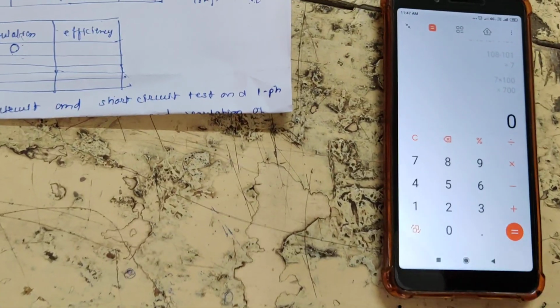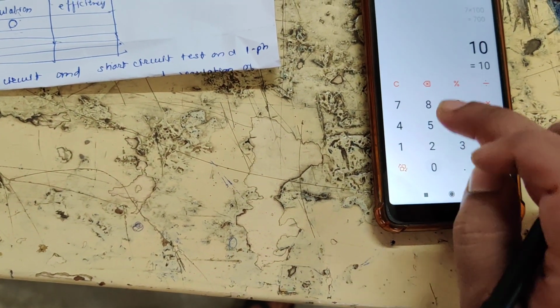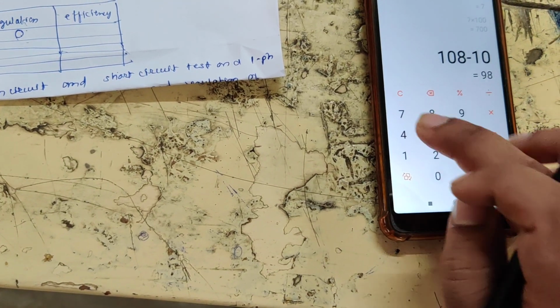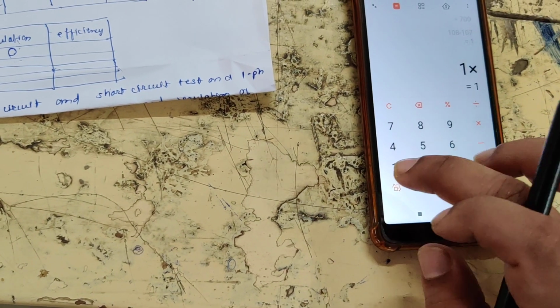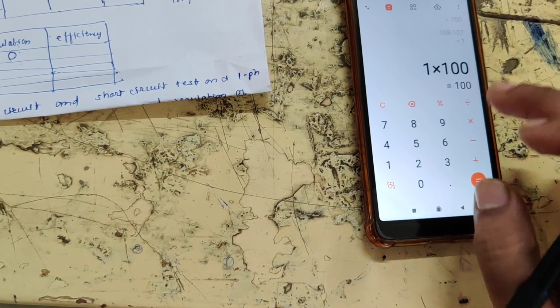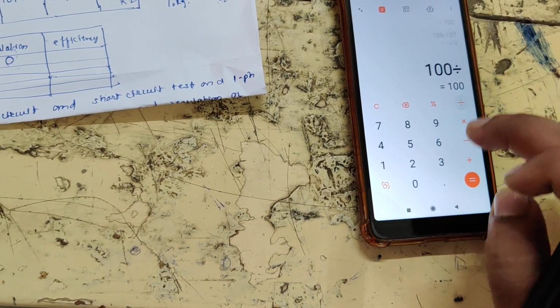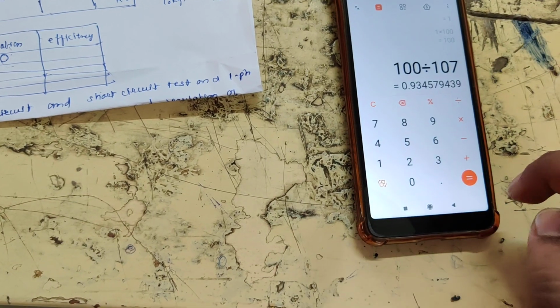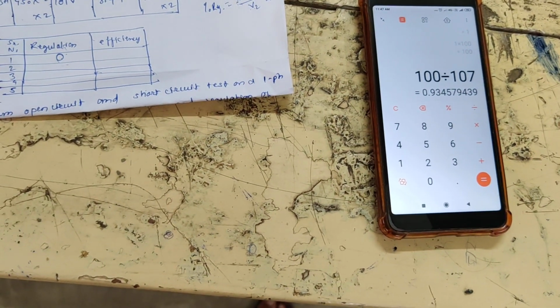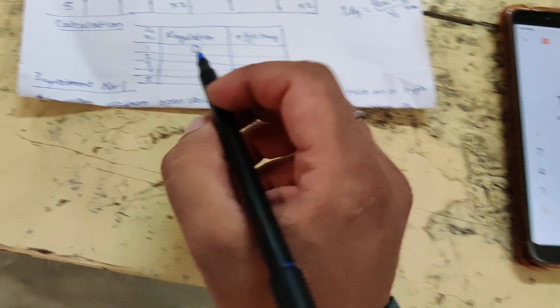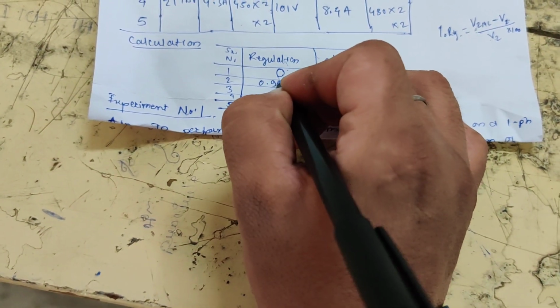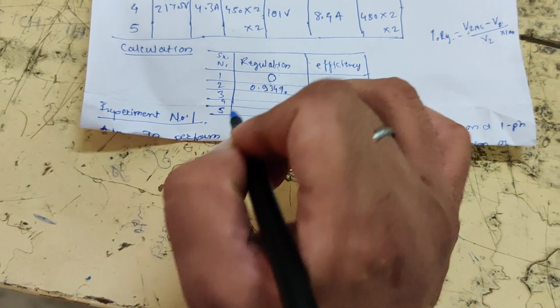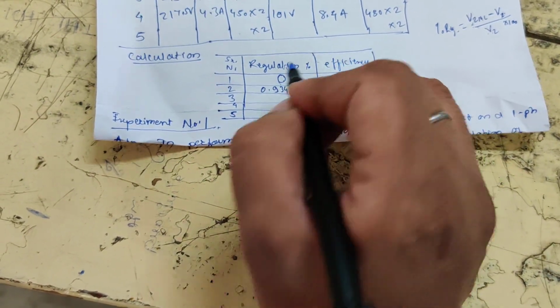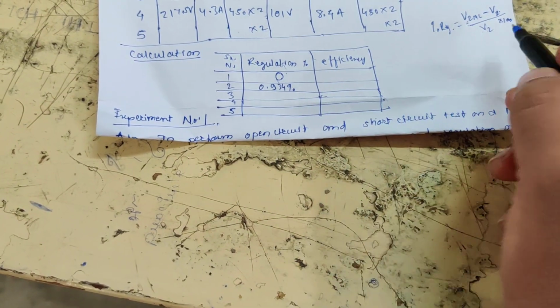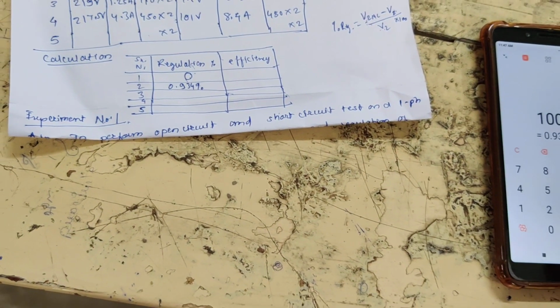So here it is 108 minus 107, multiply by 100, divided by 107. So the regulation comes out to be 0.934. So here I have to write 0.934. So this is percentage. So here we have to write it is in percentage. So 0.93%, or you may add this in per unit also.